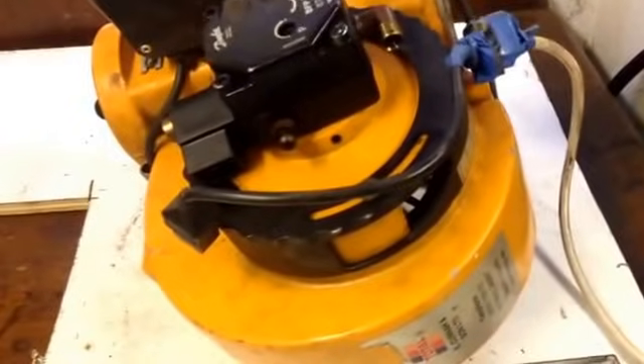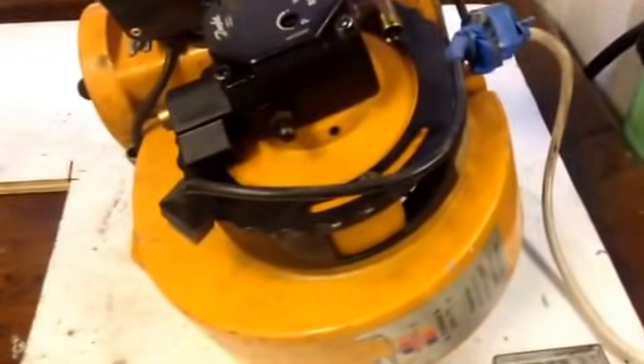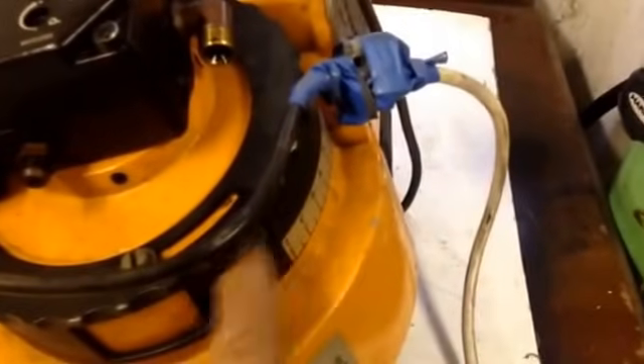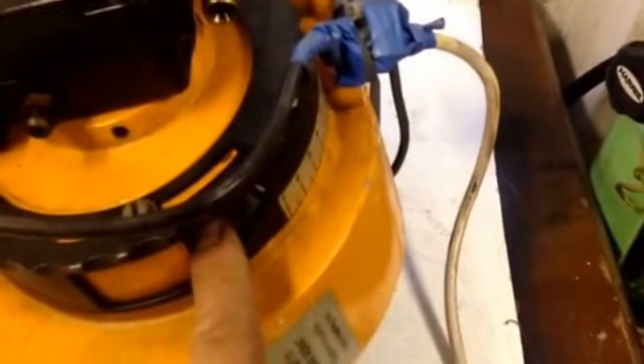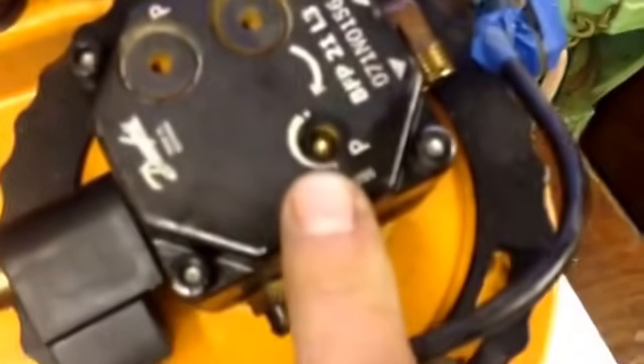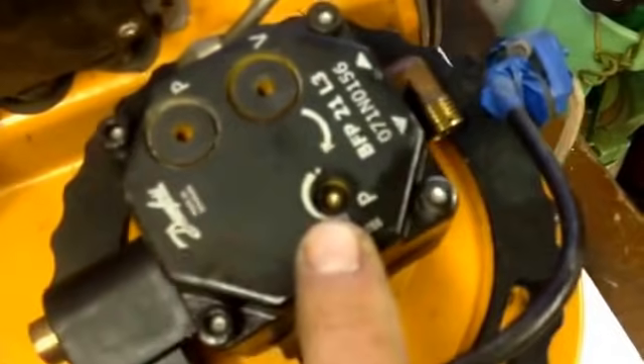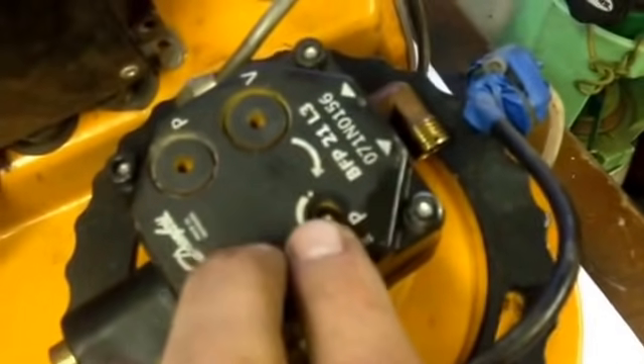Right, other things. You don't really want to look at changing the commissioning on these if you haven't got the tools and equipment, for the simple reason that you can't tell without a flue gas analyzer. So don't be changing the air-fuel mixture, the quantity of air, which is adjusted here, and don't be changing the pressure of the diesel, or the oil running through, which is there.